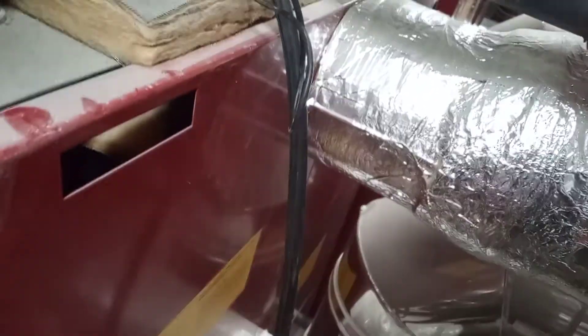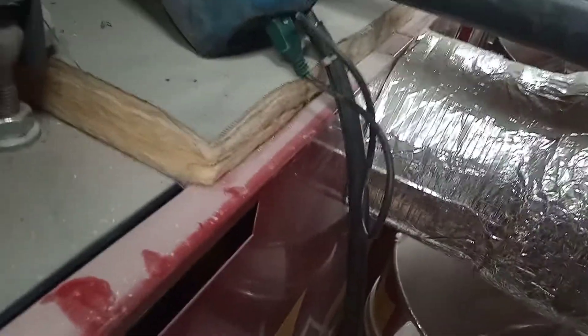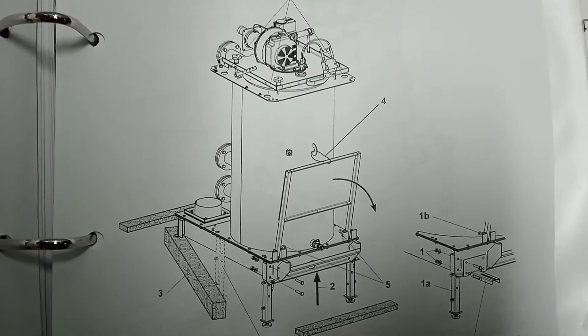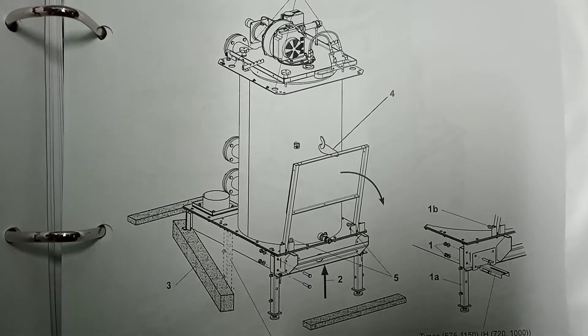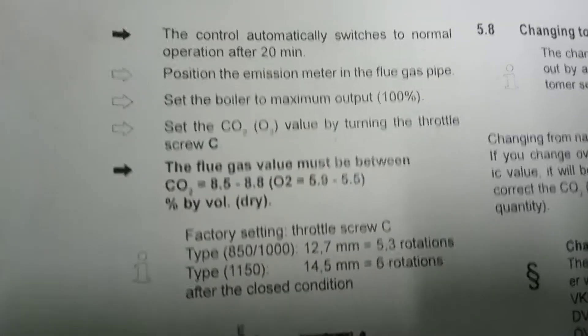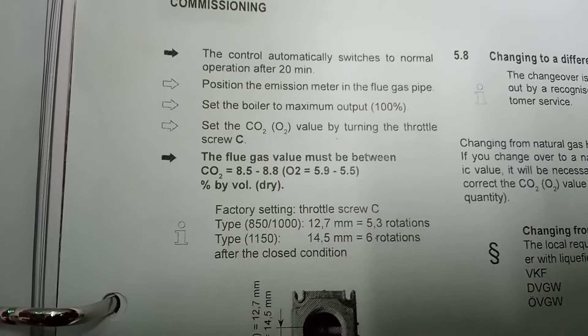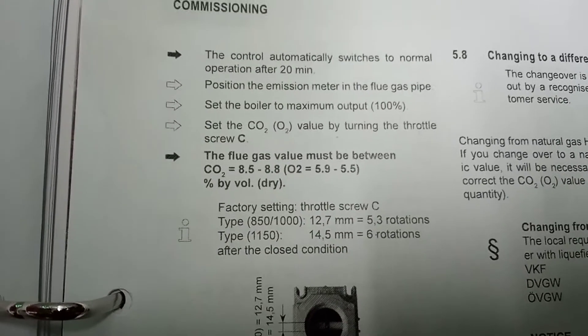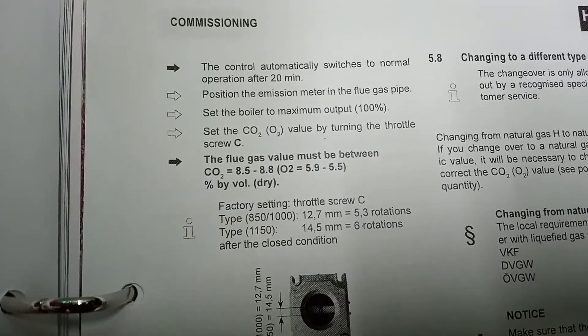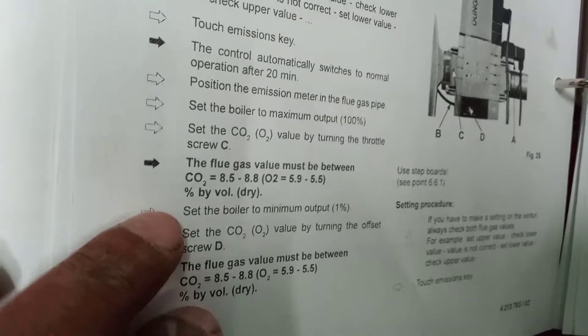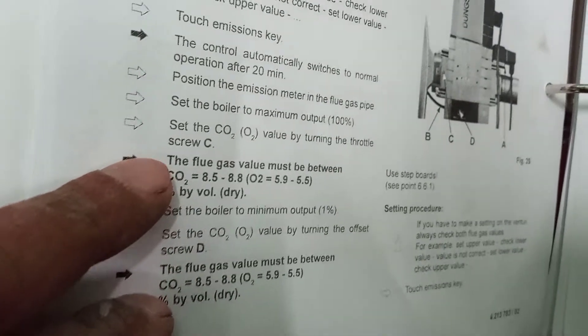Just getting my flue readings from the back and having a look at my manual. Our high fire reading should be 8.5 to 8.8 on CO2, and 5.9 to 5.5 on O2. It looks exactly the same for low fire and high fire — there's no difference.